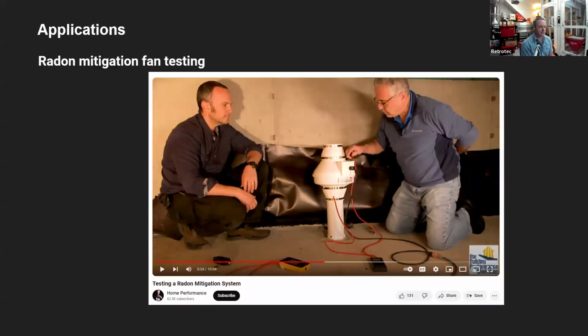And radon mitigation testing also, if you can see at the bottom of this, Corbett's there with a gentleman from Fantech, where they're testing a radon mitigation system. They've got a DM32, which works great for it. They also have a Dwyer micromanometer, but on those, they don't auto zero, so you have to make sure you zero it out each time. If not, it can give you an inaccurate reading. But now with the Solo, it's really a perfect gauge to use with that, since it auto zeroes itself out and has the precision you need to make sure that radon mitigation system is working the way it should.